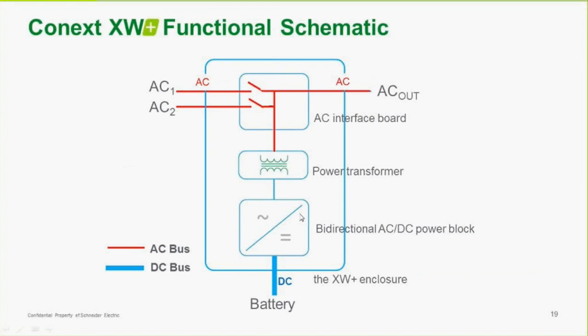This is a functional schematic for the XW Plus. There are 2 AC inputs and 1 AC output. So you'll see some more diagrams as we move on. And AC1 would normally be tied to grid, AC2 would normally be tied to a generator, and there's 1 AC out. Here's the power transformer that we were discussing a second ago. And of course this inverter is bidirectional, so it can supply power that is converted to AC, going out to a load, or it can take AC and charge the batteries either way.